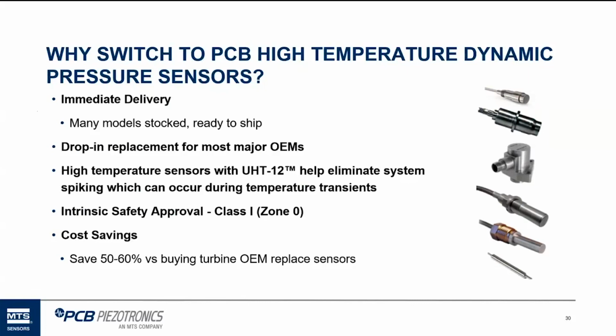The high temperature sensors are all made with our UHT12 crystal technology, which is a really good type of crystal to eliminate spiking during temperature transients, which a lot of other high temperature sensors have. When the temperature is changing, they might have some transient spikes. Our sensors are all intrinsically safe, and most of the time they're less expensive than to buy from the OEM directly.